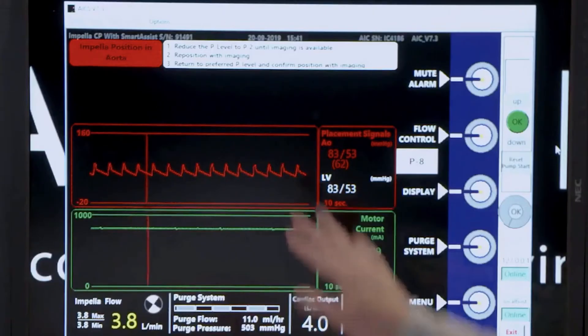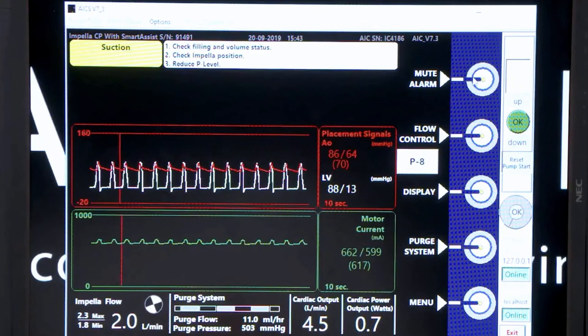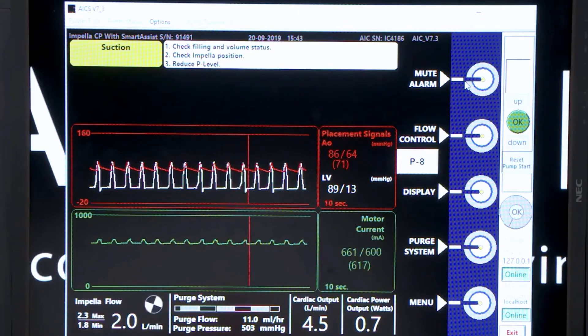The red alarm means that the pump is not functioning to support the patient, like your pump position wrong alarms. Your yellow alarm means that the pump is functioning, just not adequately supporting the patient. This is going to be more like a suction alarm.